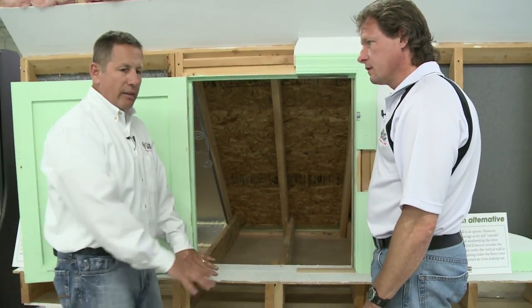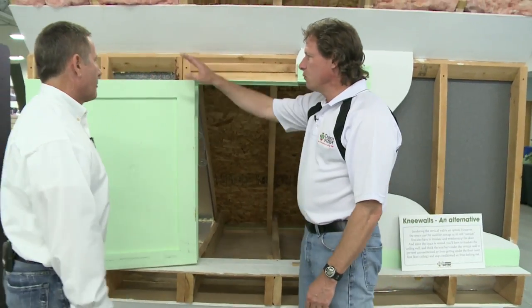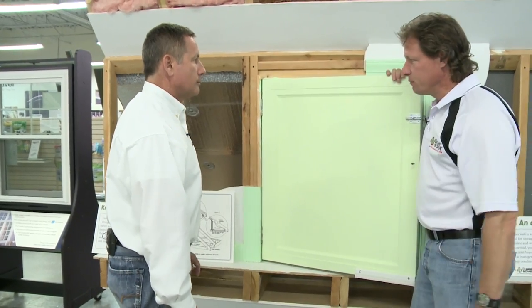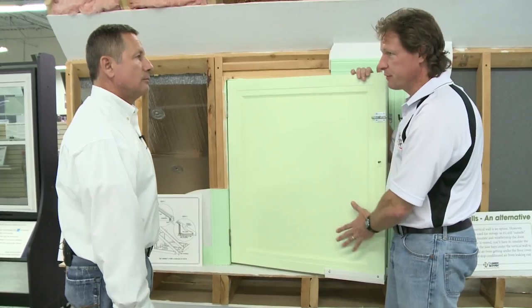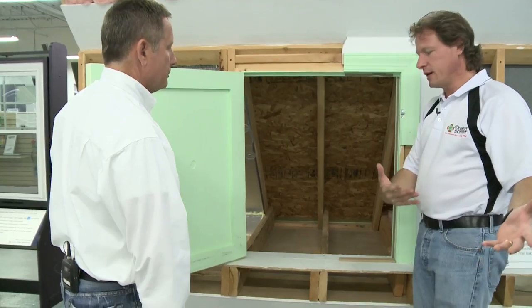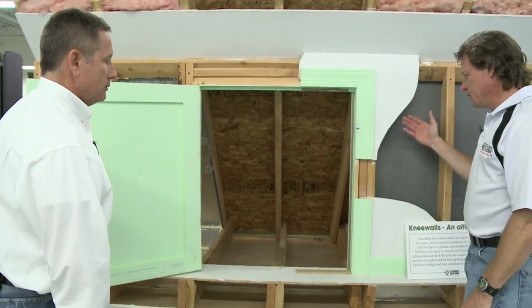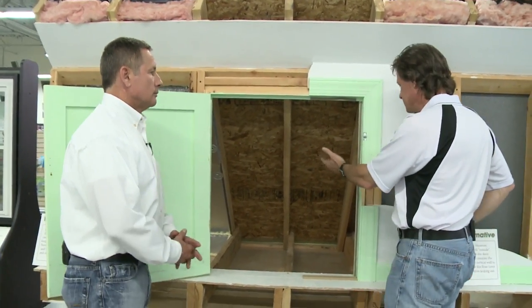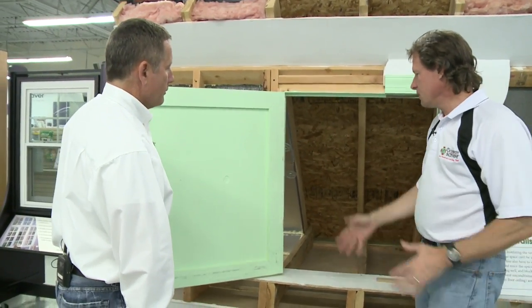If this is a bedroom up here, then all winter long that floor is going to be real cold. And when they build little doors for these knee wall spaces, they'll just put a panel of plywood or an interior door panel — it's not an insulated exterior door, nor is it sealed. So air leaks through and it's a cold spot. And these walls are typically poorly insulated or they just have some fiberglass leaned up against the inside of the walls. So lots of problems.